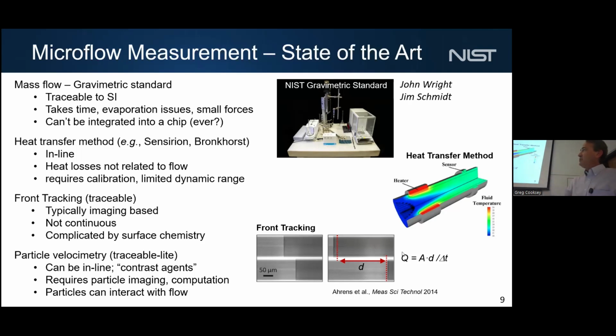The most common commercial device is based on heat transfer. So you have a heater inside a microcapillary and a sensor downstream, and you're just calibrating that transduction of heat over time. But of course, you've got heat losses that don't have anything to do with the flow. And so that really limits your ability to dynamically and carefully measure small mass flow rates.